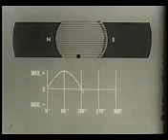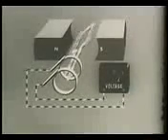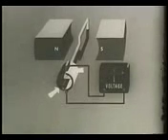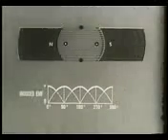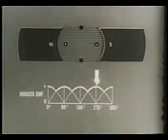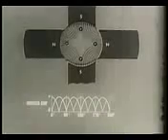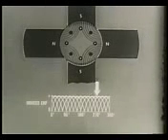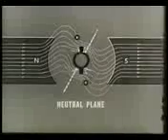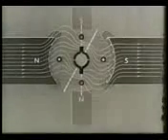All generators are basically alternating current generators and produce AC internally. The basic AC generator becomes a DC generator when a commutator is attached to the conductor. Each commutator segment rotates with its respective conductor, producing a direct current. This current, which is a pulsating current, is made smoother by the addition of more magnets and more loops. Sparking in a generator is sometimes caused by a shift in the neutral plane. This can be corrected by adjusting the brush position, or by the use of interpoles and compensating windings.